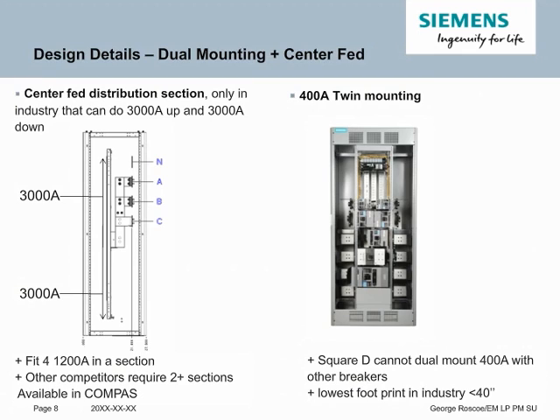At 30 inches deep, this option requires the top WL cables to go out the top and the bottom WL cables to go out the bottom. This section saves up to 38 inches of space, and in COMPAS it's easy to configure by selecting 2 key options.